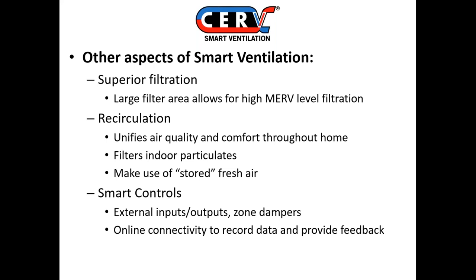The recirculation mode is another important, unique aspect of the CERV. When you don't need fresh air, that recirculation mode lets you do things inside that you couldn't with a once-through system. So it helps to unify air quality and comfort throughout the home. You can filter indoor particulates and scrub the indoor air without introducing new particulates from the outside. And you can make use of stored fresh air. So in spaces in the house that don't have high pollutant levels, mixing the air continually through the space, you can make use of that stored fresh air to delay needing to bring extra air in from the outside.